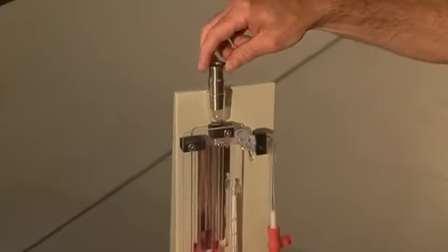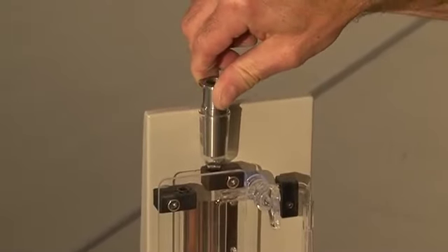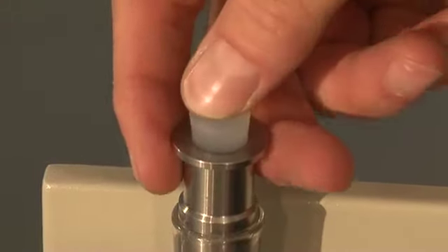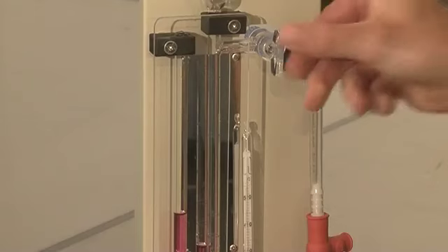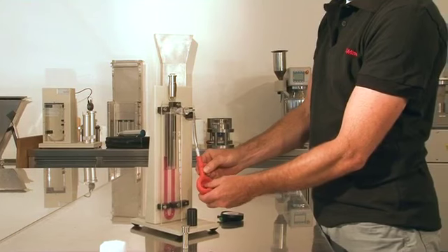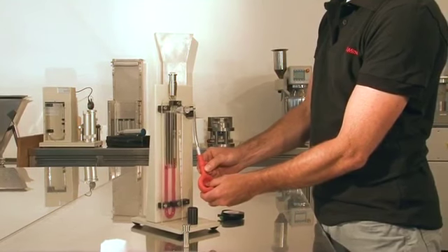If the cement bed has been correctly compacted, the outer lightly greased tapered surface area of the cell is inserted into the tapered opening of the U-tube. The cell is hermetically sealed with a plastic plug. Open the stopcock in order to permit the suction process of the manometer liquid with the aspirator bulb.